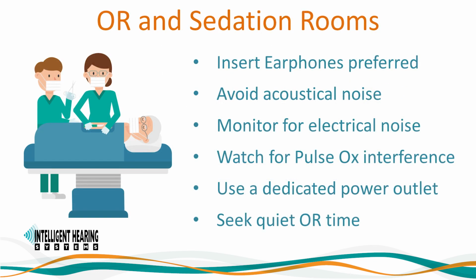Testing in a sedation or operating room has its own set of recommendations. Operating rooms are usually acoustically noisy. Insert earphones help attenuate ambient noise and are safer in cases where blood could make an electrical connection between the patient and the transducer. But the insert earphone transducer should be held with a drip stand at a higher level than the tip to avoid blood entering the transducer under gravity.